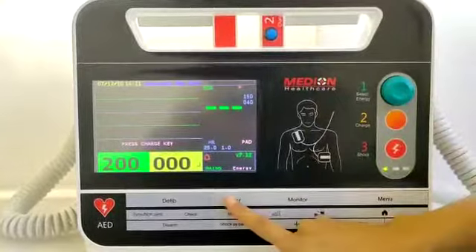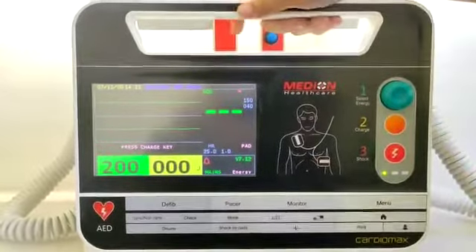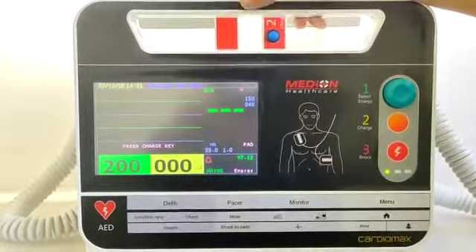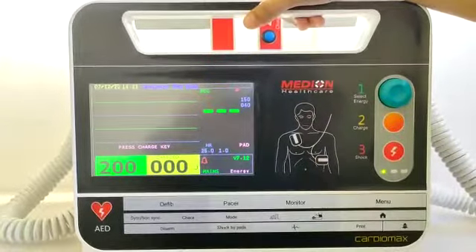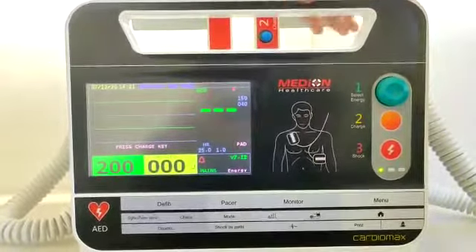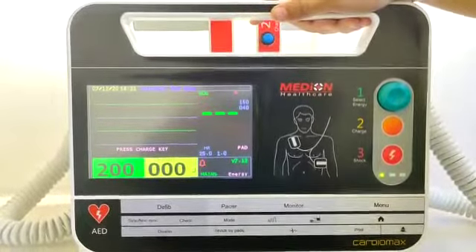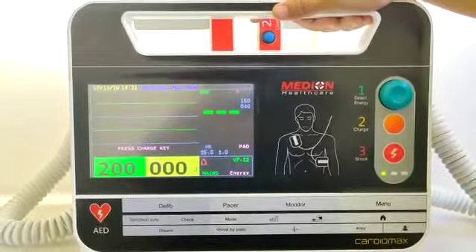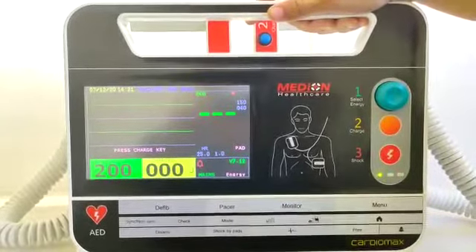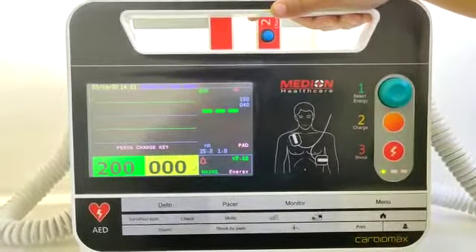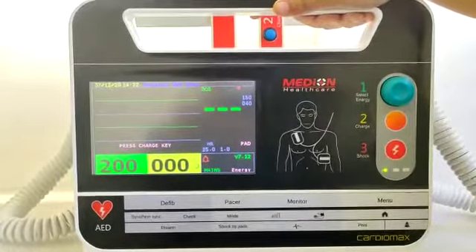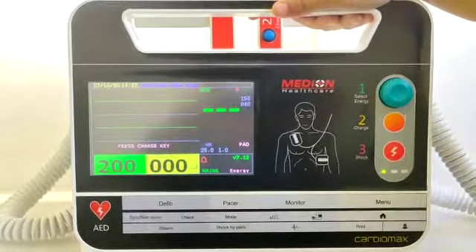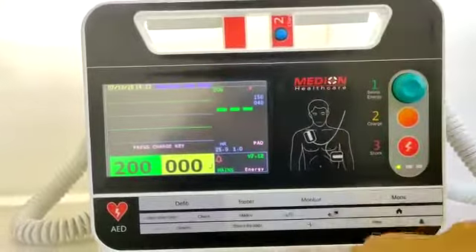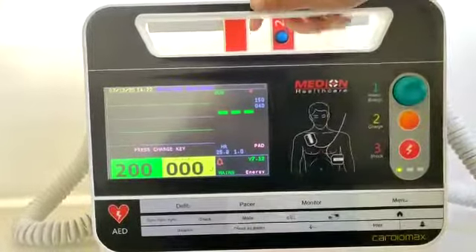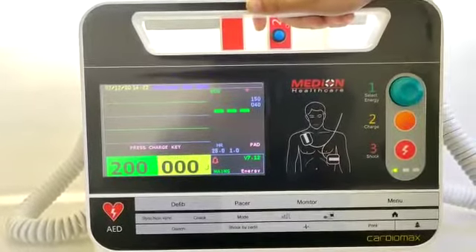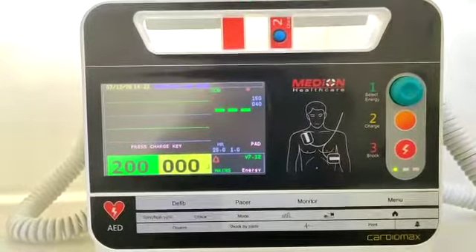Next is pacer mode. In pacer mode, there are two operational modes, demand and non-demand. In demand mode, the pacer will sense the patient's intrinsic heart rate and will provide pacing if the intrinsic heart rate is lower than the set rate. Whereas in the non-demand mode, the clinician will set the rate regardless of the patient's intrinsic heart rate. Next is the shock by pad feature. This feature will be used in an emergency when the user needs to give a shock through pads in pacer mode.